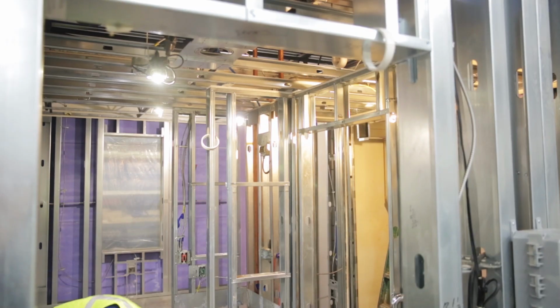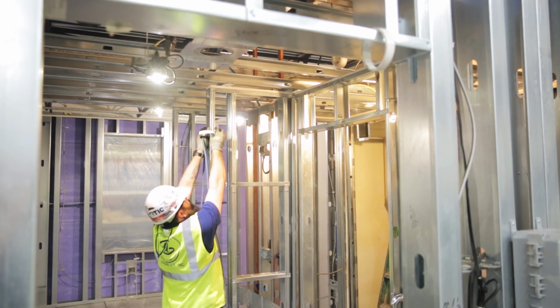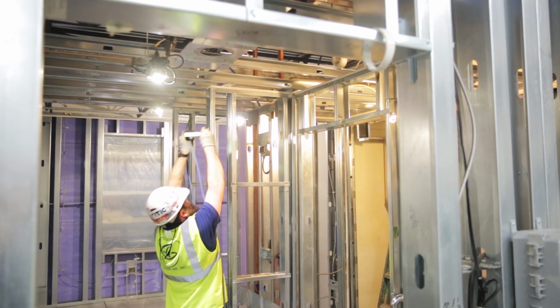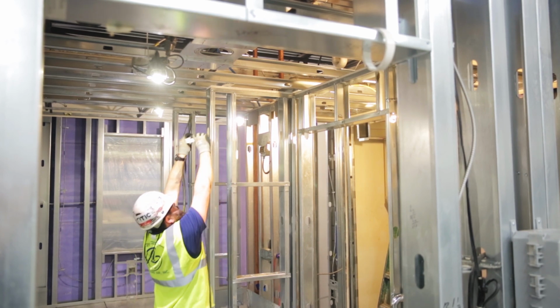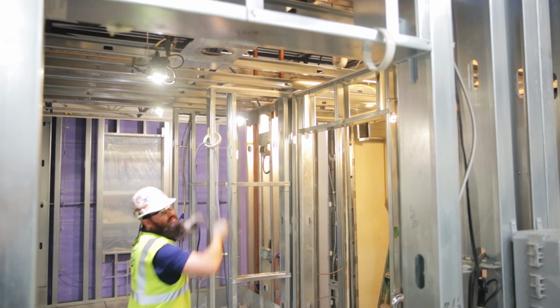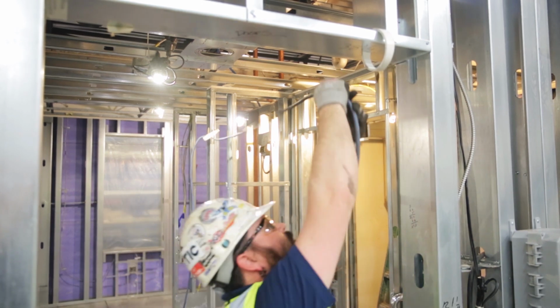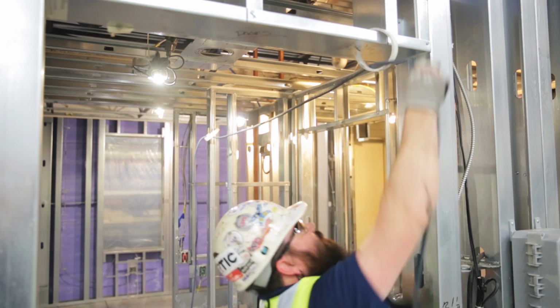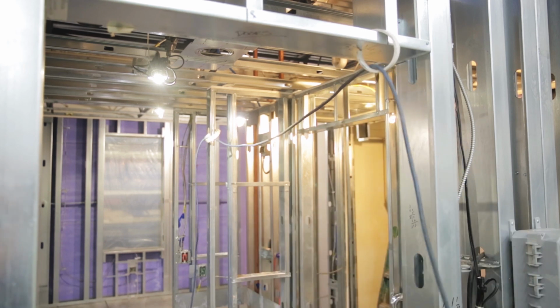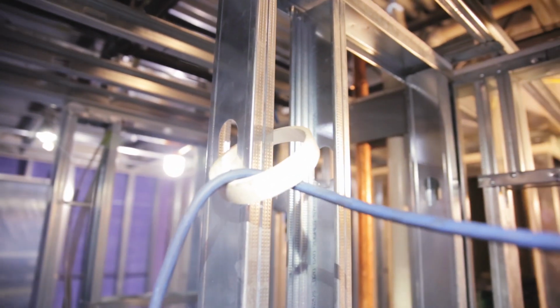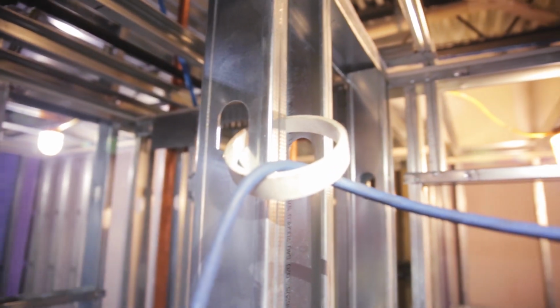When a cord connector is wet, electric current can leak to the equipment grounding conductor and to those who pick up that connector if they provide a path to ground. Electric leakage can occur at any wetted area of the cord. Limit exposure of connectors and tools to excessive moisture by using watertight, sealable connectors and elevating extension cords in wet conditions.